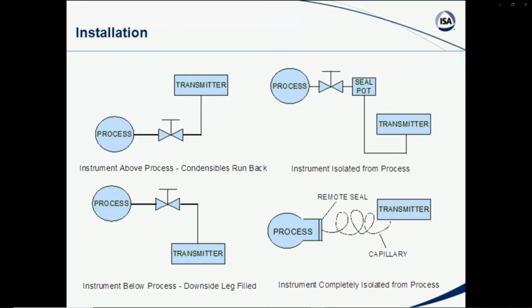On previous exams, I know I've seen questions that deal with how do you install some of the units and devices that you'll run into. This is a sketch of different types. For instance, this first one, the instrument's mounted above the process. We have the instrument mounted above the process, and that is really for the purpose of a gas or a vapor measurement. It would allow any condensables to drain down and back into the process or to the tank.